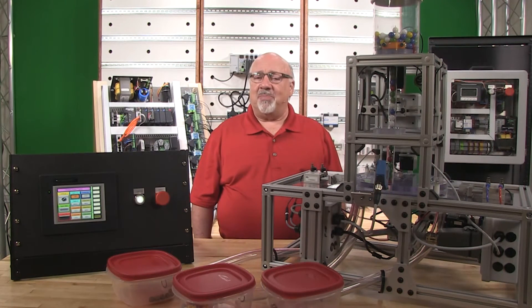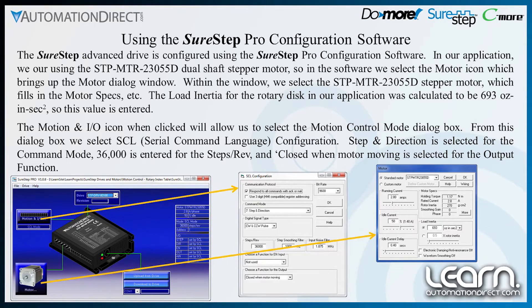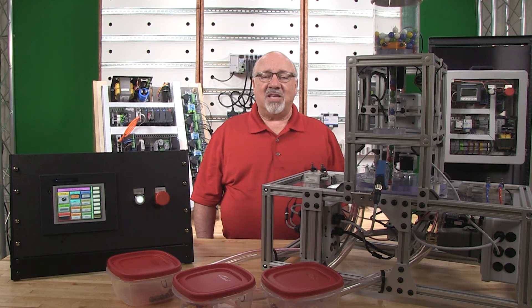The SureStep Advanced Micro Stepping Drive has the ability to be set up using the SureStep Pro configuration software. In our example, we select the SCL configuration as our motor control mode, use the step and direction command mode, set our steps per revolution to 36,000, and choose an output function of 'closed when motor moving.' We will use this signal wired to a DC input to know when our index cycle is completed and allow us in the ladder logic to sequence other events to take place. One of the nice features of the software is that we can save the configuration as a file for later use. We have also included the SureStep Pro configuration software file as a downloadable takeaway.